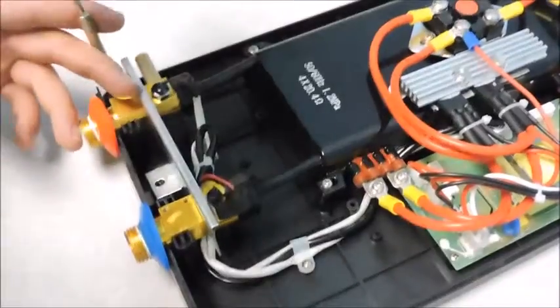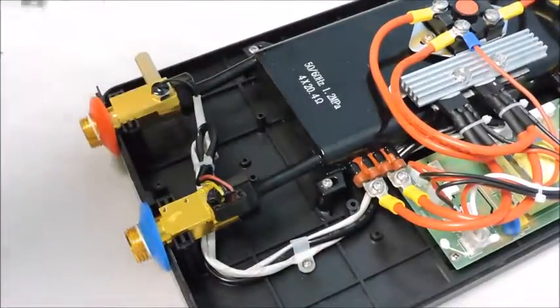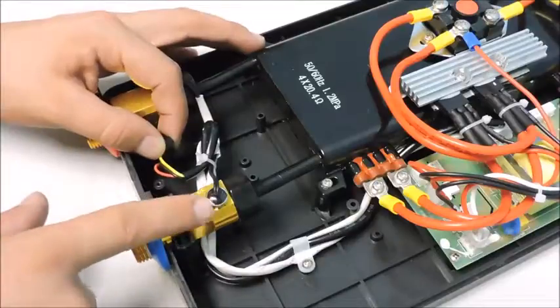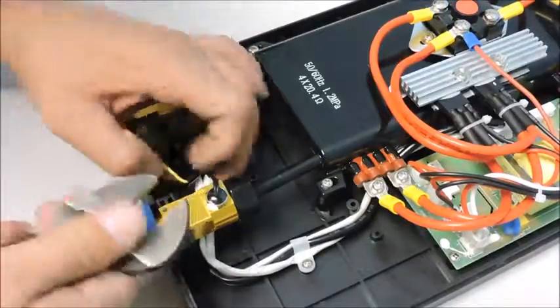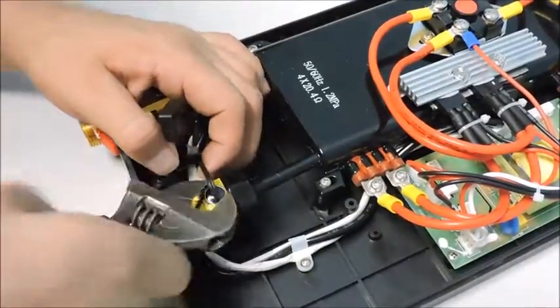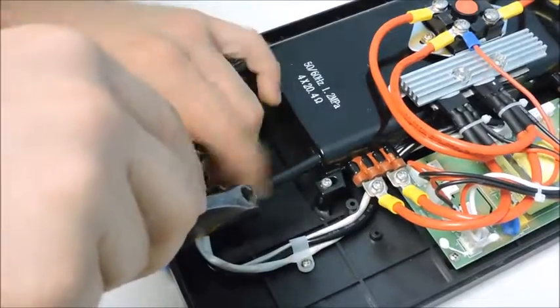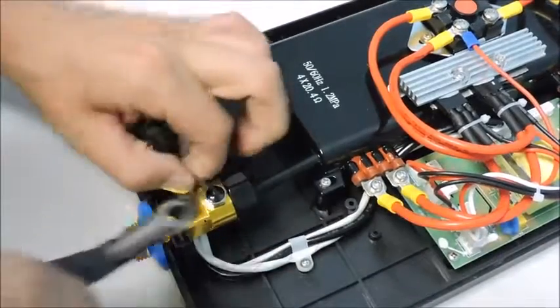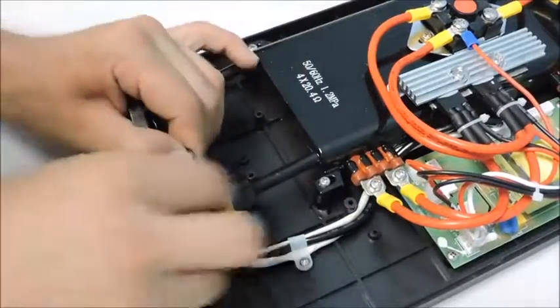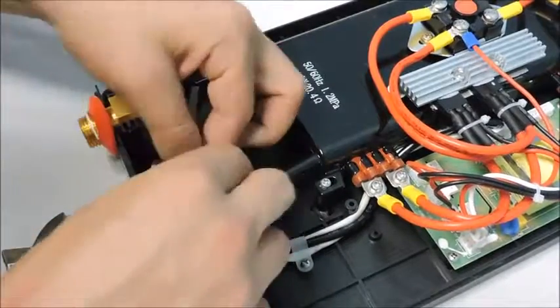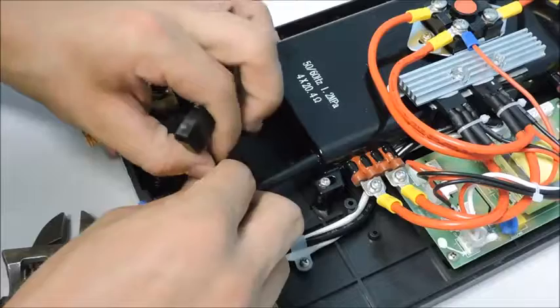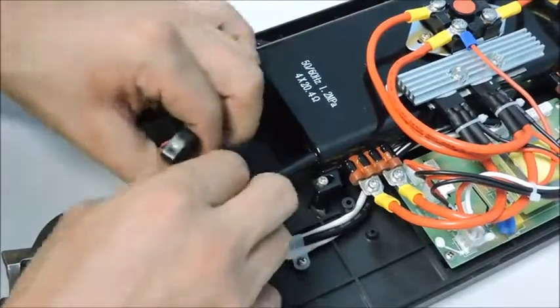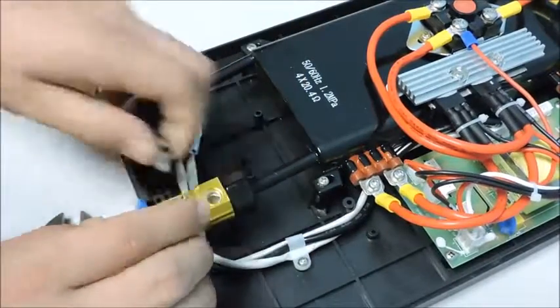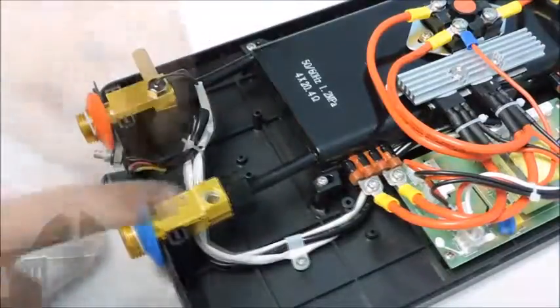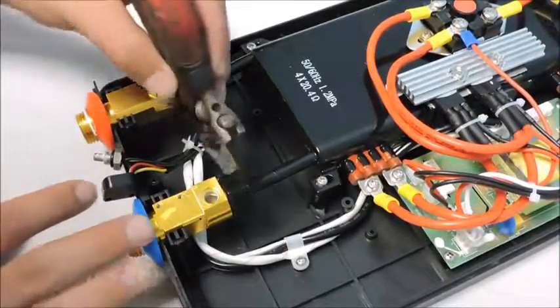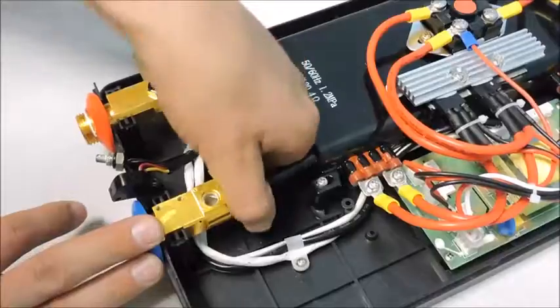You can choose to disconnect the inlet temperature sensor from the PCB, but in this example, we will show you how to do it while leaving it connected. While unscrewing, make sure that the wire twists evenly throughout the length of the wire and is not isolated to just above the sensor, or it may break. Now, loosen the connection on the heat exchanger to remove this fitting.